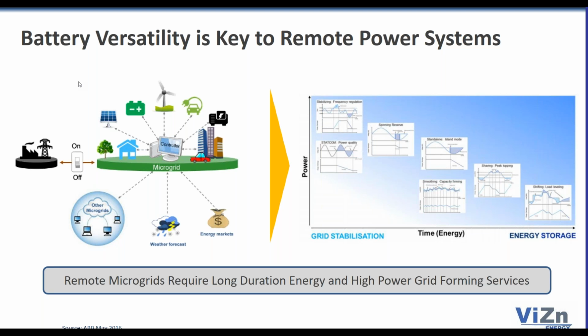How much less fuel? It tends to vary anywhere from 7 to 15% less fuel. The other nice thing about adding storage is that you can drive renewable energy penetration in that application above 15 to 20%, and you can push it all the way up to 70 to 80%, cutting your diesel usage by 70 to 80%.